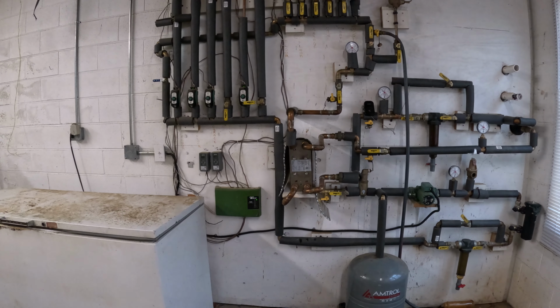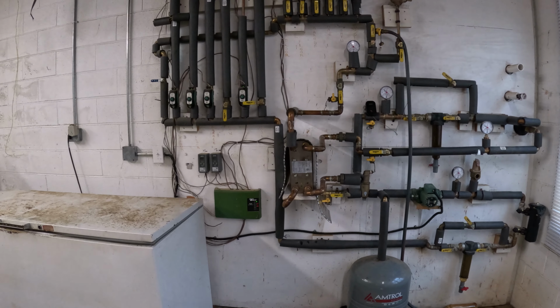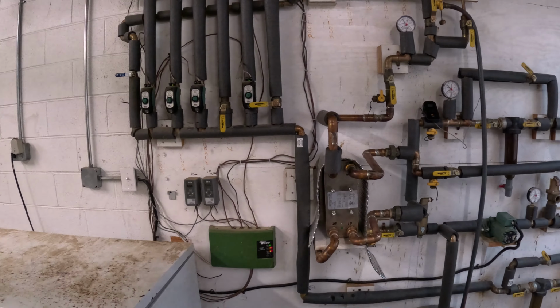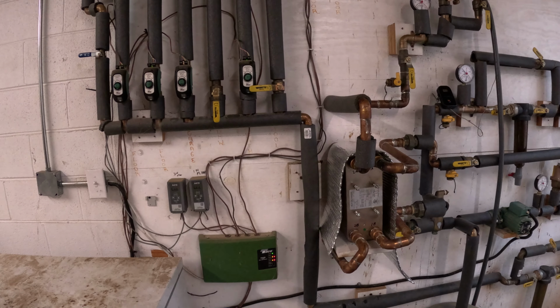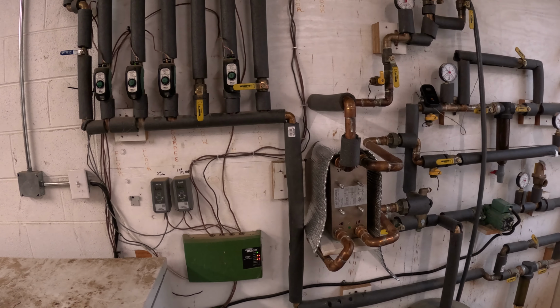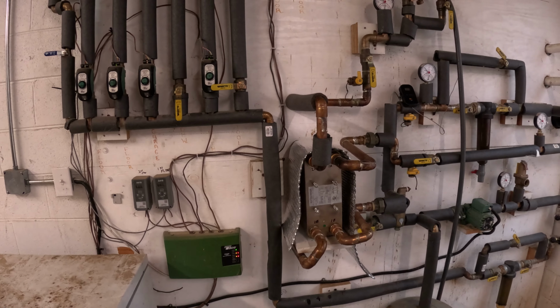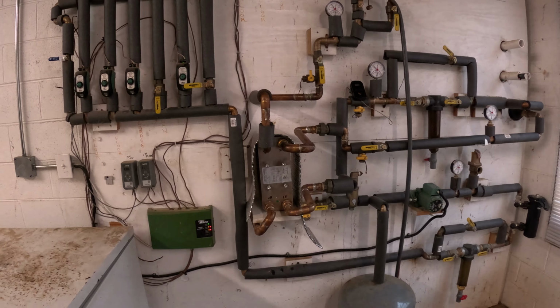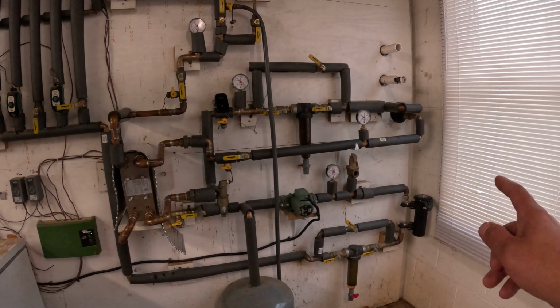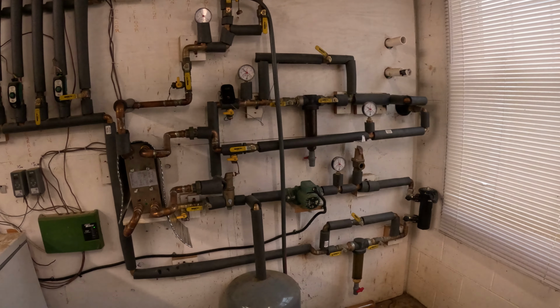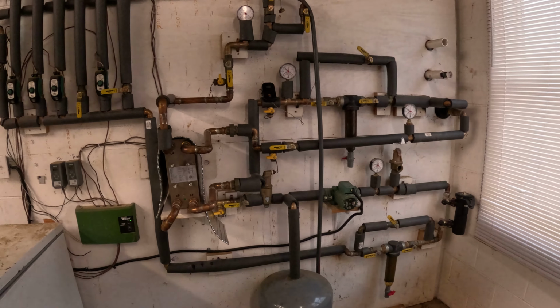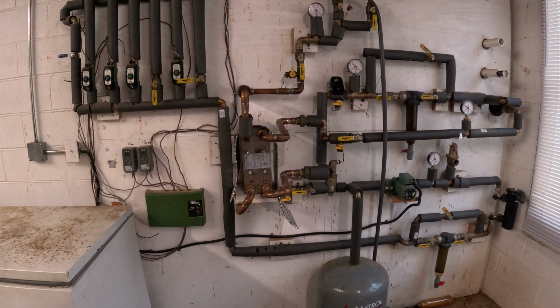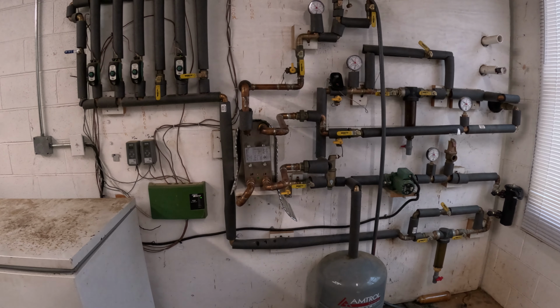I did have to change out that heat exchanger last year. That's kind of why it looks a little different. I had to cut and redo that, and a lot of that was because of not knowing about the corrosion that happens in closed loop systems, and I didn't have that magnet filter in there. We started losing that heat transfer capability, and it caused problems, but I think we got it corrected now.